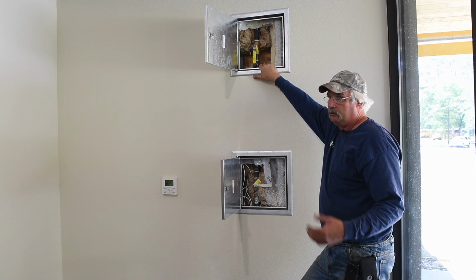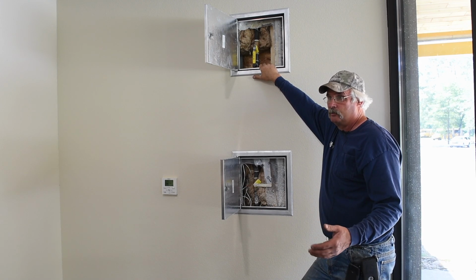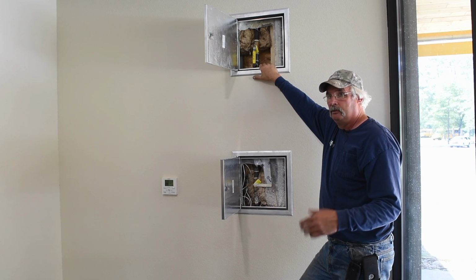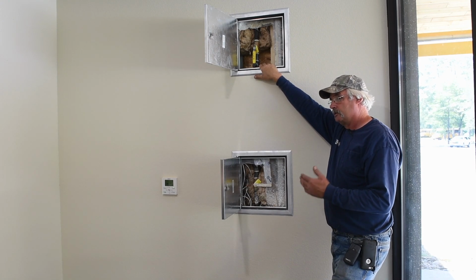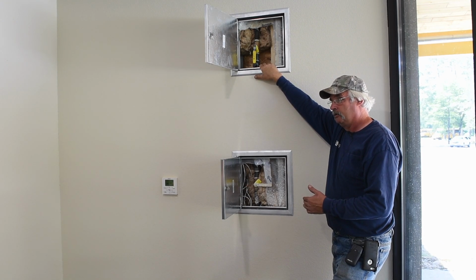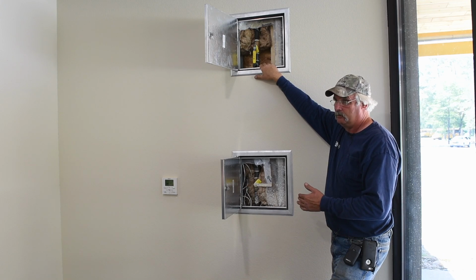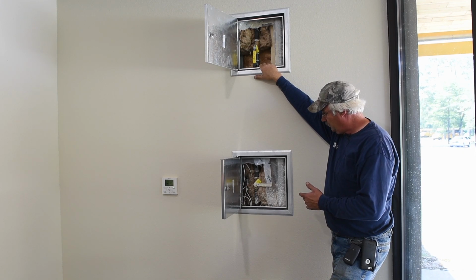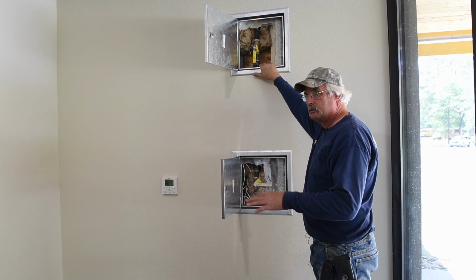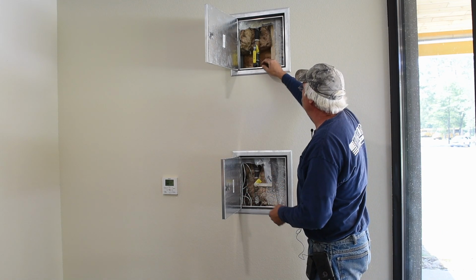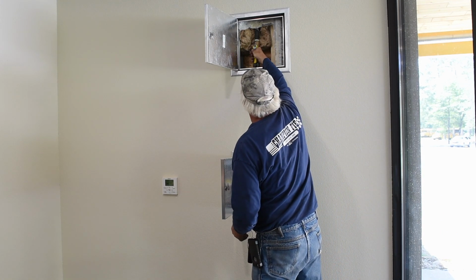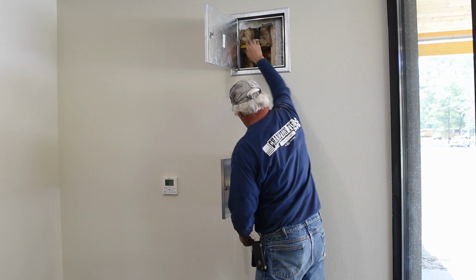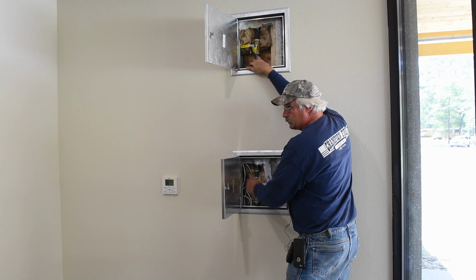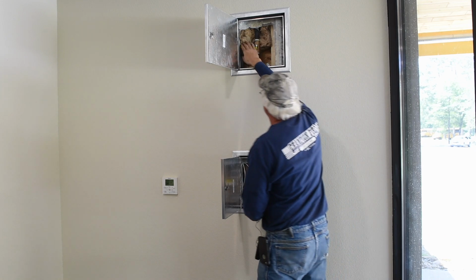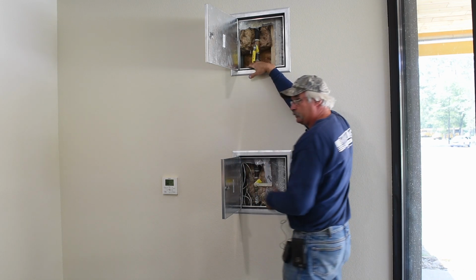So if you lost the heat, the air compressor went out, whatever, the dry system tripped, somebody opened a valve they shouldn't have, you have to make sure the system's all drained down properly. So this is done by care and maintenance. So at that point, you have to set the system back up, keep working these 2 valves. So you'd have to close this control valve, drain any moisture out that goes down and out, and keep reversing the process until you get all the moisture out of your system.